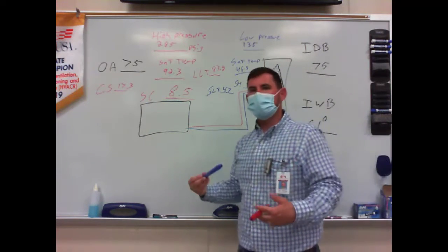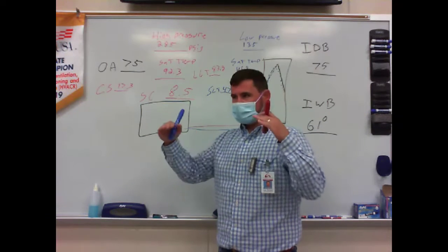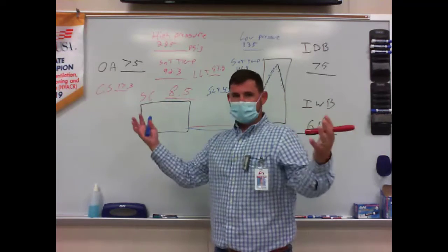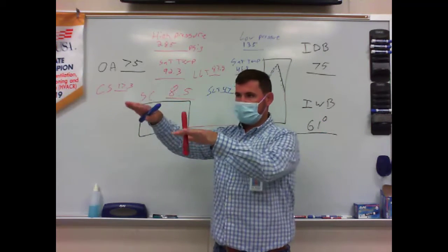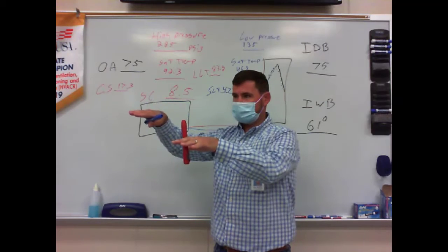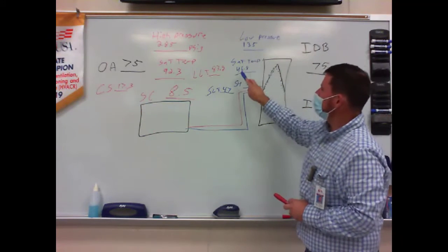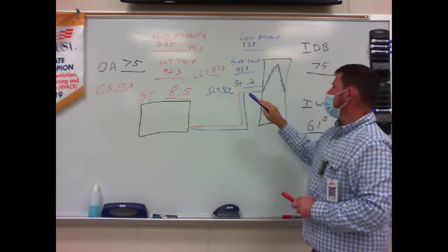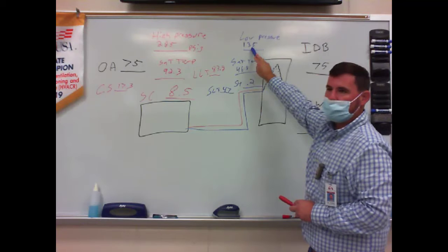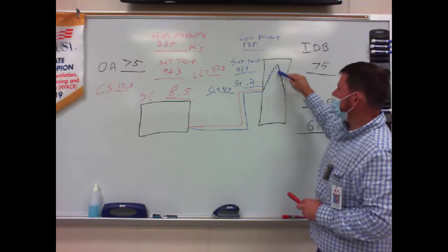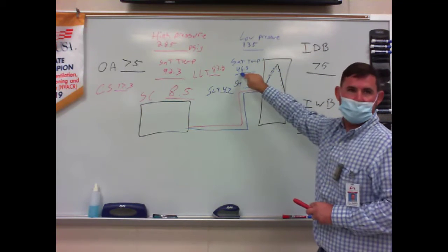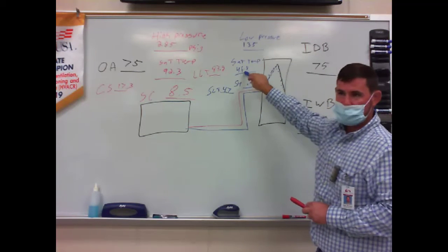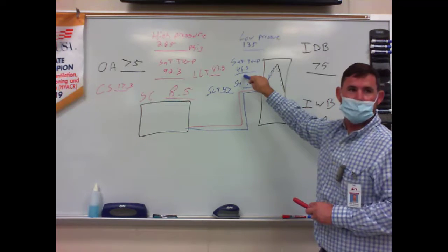That's why we got to let it run for a good 10 or 15 minutes for it to stabilize, for it to get to that point where it's bringing in new liquid and it's boiling off the existing liquid into a point of pressure that's consistent. Once we know that pressure, we know the temperature that it's saturating at. We know its boiling point. So the whole time at 135 psi, as we're going through here, we're staying at 46.8 degrees. Our liquid is turning to a vapor, and that's staying at 46.8 degrees, right?